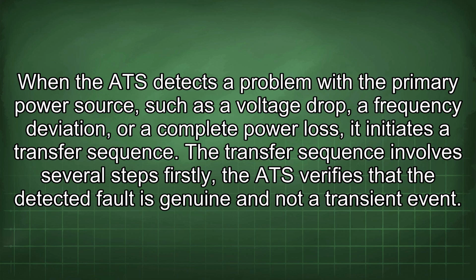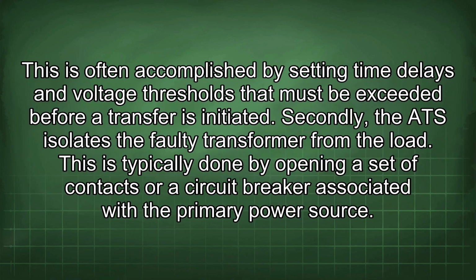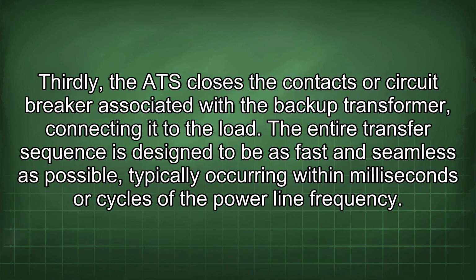The transfer sequence involves several steps. Firstly, the ATS verifies that the detected fault is genuine and not a transient event. This is often accomplished by setting time delays and voltage thresholds that must be exceeded before a transfer is initiated. Secondly, the ATS isolates the faulty transformer from the load. This is typically done by opening a set of contacts or a circuit breaker associated with the primary power source. Thirdly, the ATS closes the contacts or circuit breaker associated with the backup transformer, connecting it to the load.